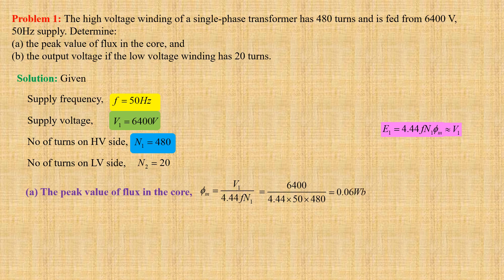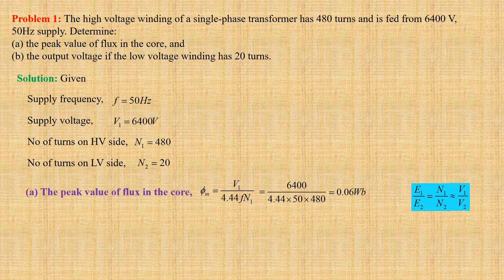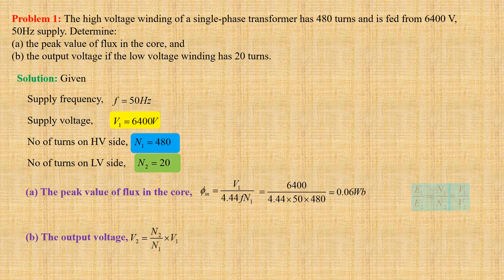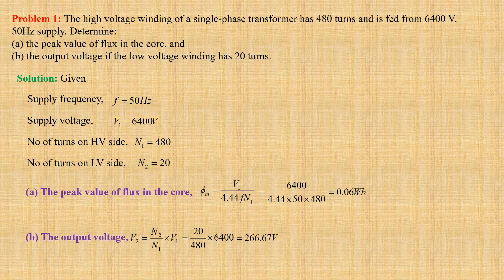For a single phase transformer, E1/E2 equals N1/N2, which is approximately equal to V1/V2. The output voltage V2 equals N2/N1 × V1. Using values we get 20 divided by 480 × 6400, that gives us 266.67 volts.